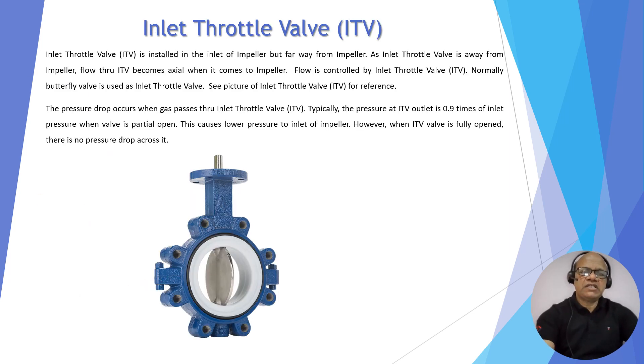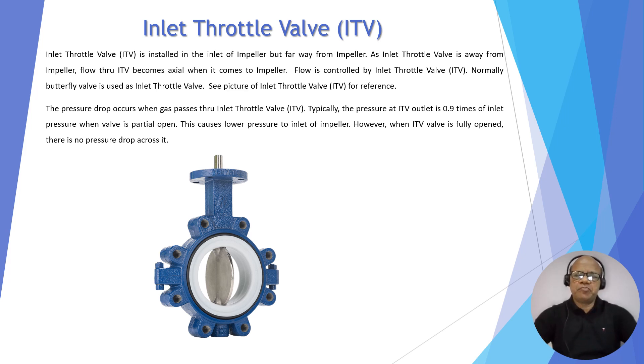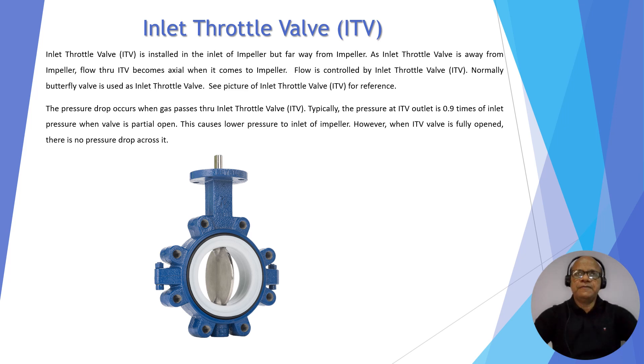ITV is just a butterfly valve — any type of butterfly valve can be used as an ITV. The big disadvantage of using ITV is there is a considerably large pressure drop as compared to IGV. Typically, the pressure drop across ITV is 0.9 times of inlet pressure — that means if the inlet pressure is 10 bar, you will get only 9 bar at the outlet of ITV, which is the inlet to the compressor. So the performance of the compressor will be affected if you use the ITV. However, ITV is cheaper cost-wise than IGV.